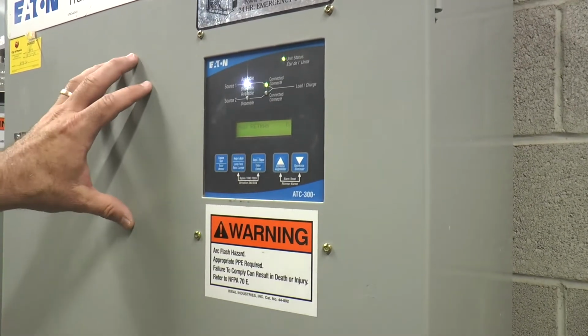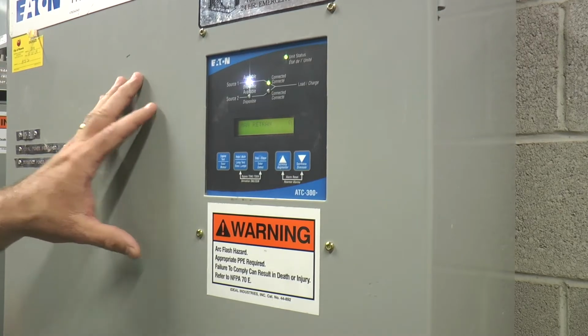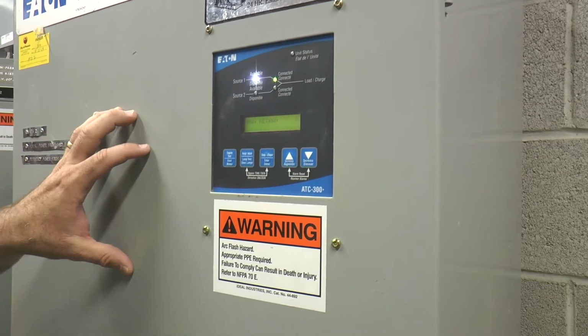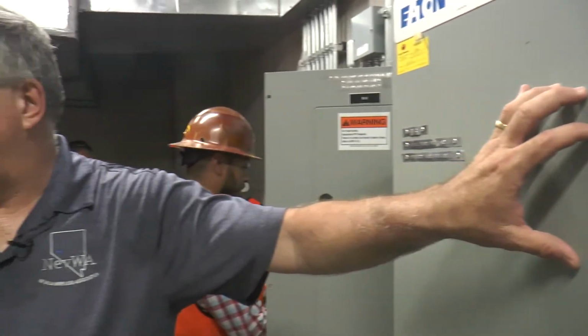Now, if this transfer switch is also connected to the elevators, there's two contacts. There's a contact for switch position and a contact for pre-transfer signal. The pre-transfer signal lets the elevator know that it's going to switch from one source to the other, and that timer's set up at 20 seconds. So once we give the elevator a command that we're going to transfer, they stop a car, open the door, wherever that is in their cycle. Once the transfer switch transfers over, we close another set of contacts to tell them that they're on emergency. At that point, they only run 2 elevators. The third elevator, if I remember correctly, will come all the way down to first floor and open up, with whatever the protocol is for that.